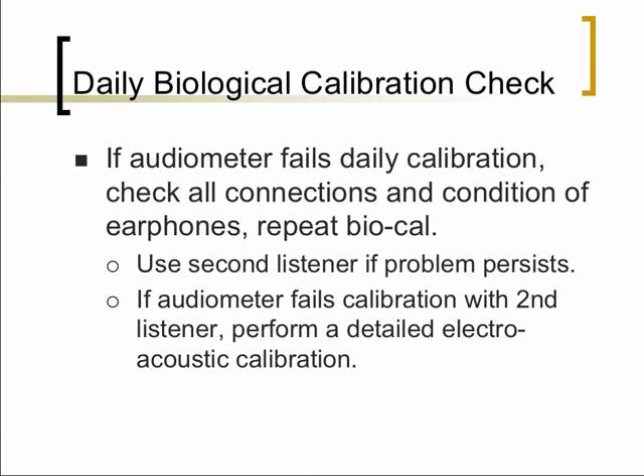If the audiometer fails the daily calibration, in other words, if those thresholds shift with no particular reason from the patient that you're using, you would check all the connections and the condition of the earphones and repeat this calibration. In case the differences persist, then you would want to use the second person that you have in reserve. And if that was the same case for the second person, if the thresholds seemed to have shifted dramatically or significantly, then you would perform this detailed electroacoustical calibration again.